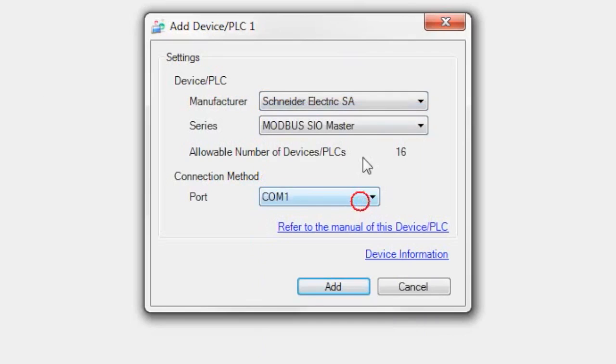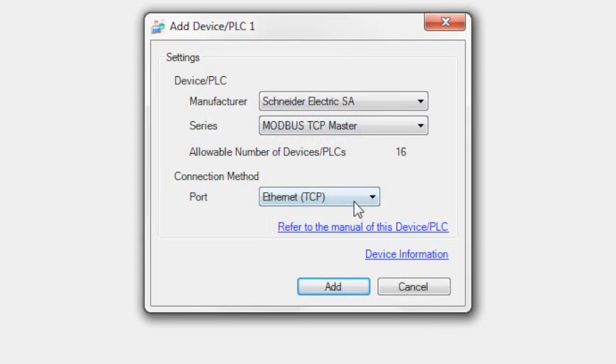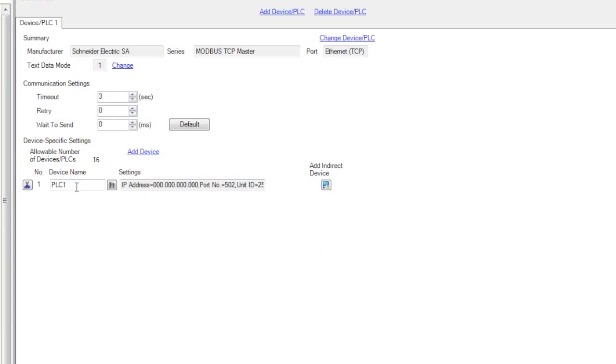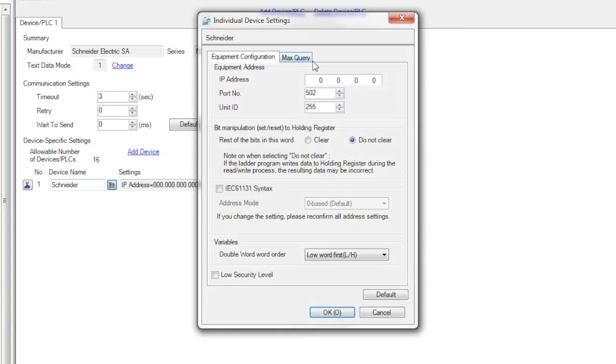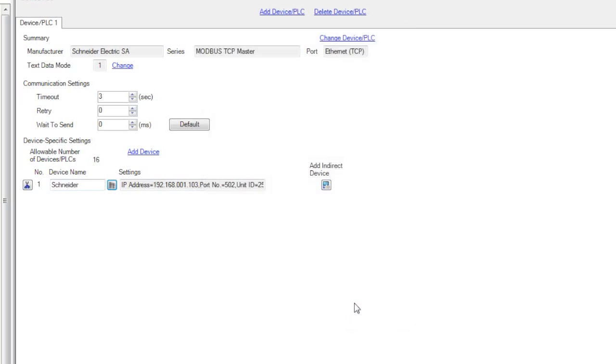If I select Schneider Electric, I'm going to select TCP Master, say OK, and here I'm going to give it a name. Now I'm going to type in the IP address of the PLC, which is 103. I'm going to say OK, and that's pretty much it. I would leave the default settings here to start.